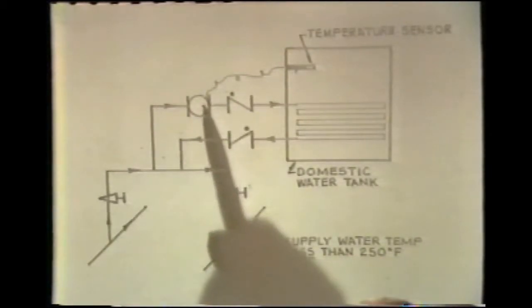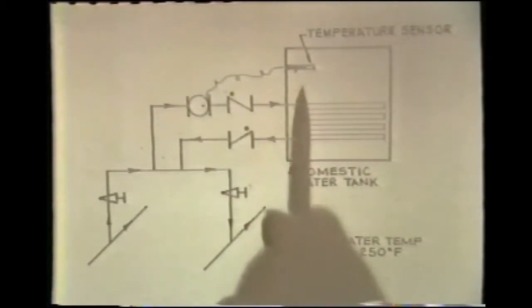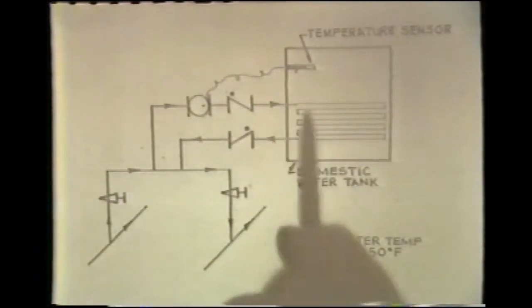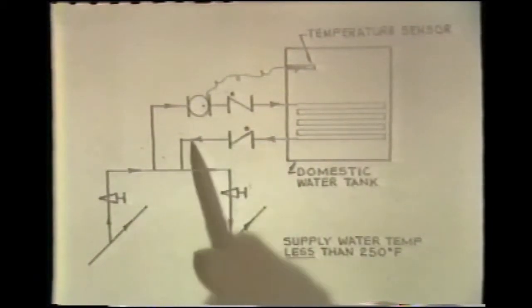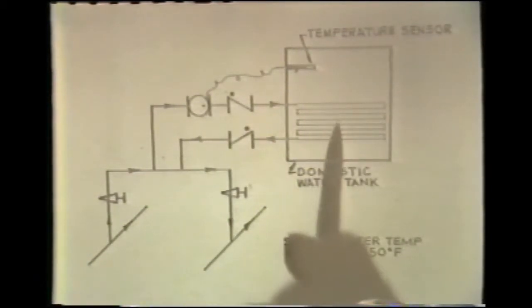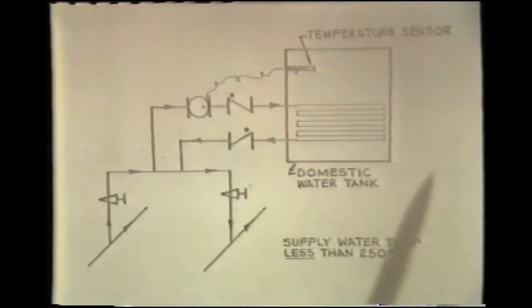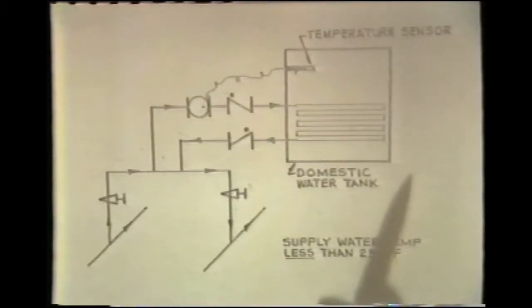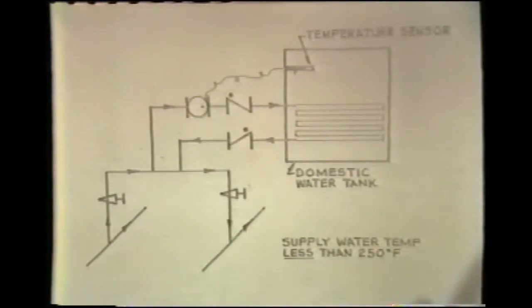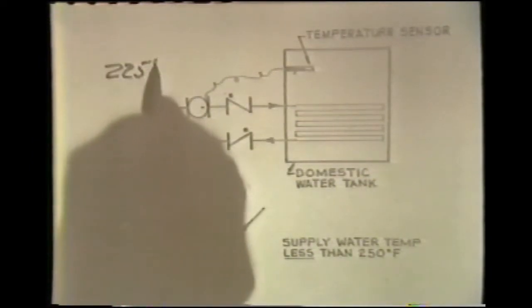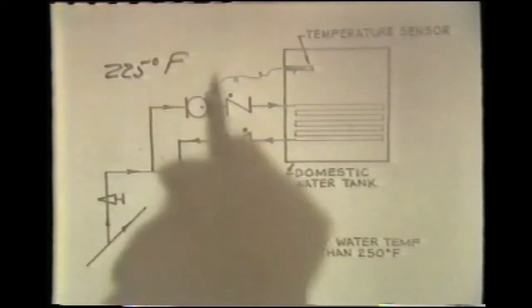When the temperature control tells the pump to start, in order to maintain temperature, the pump simply starts, drives water through the heat transfer in the storage tank, providing the necessary heat. This would be used for water temperatures less than about the order of 225 degrees Fahrenheit.